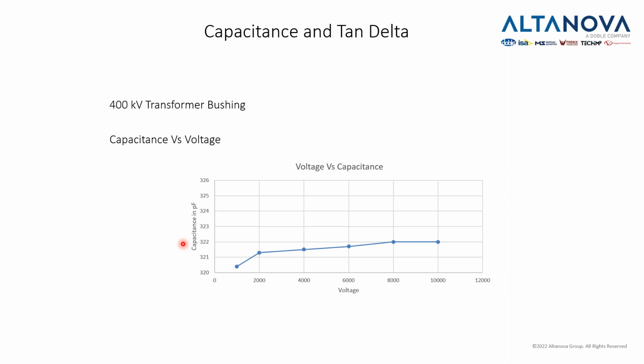Why am I saying this? Because somebody can rightfully ask, well, can I test a 400 kV transformer with 12 kilovolts? Yes, you can, because up to 10, 12 kilovolts is practically all you need for the insulation to have all the molecules inside polarized.